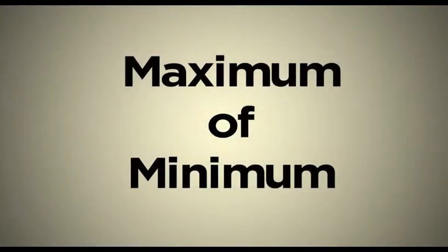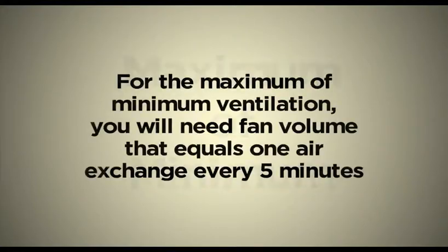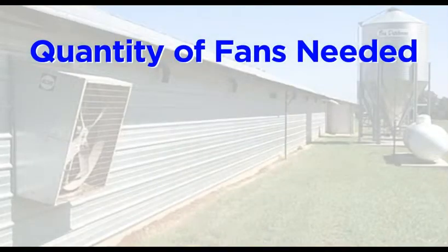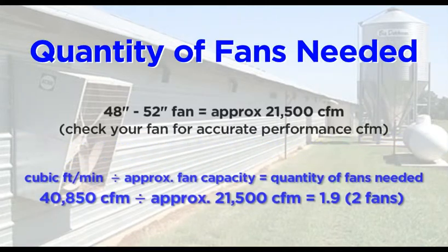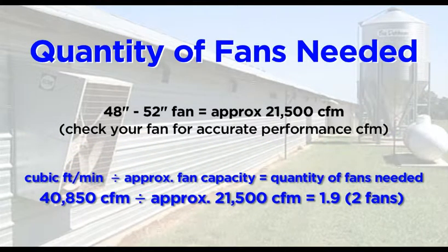For the maximum of minimum ventilation, you will need fan volume that equals 1 air exchange every 5 minutes. To determine the number of fans needed, take the cubic volume of the house and divide by 5. Then divide 40,850 — the cubic volume of the house divided by 5 — by the amount of air one summer fan can displace in cubic feet per minute. Always round up or down to the nearest whole number.